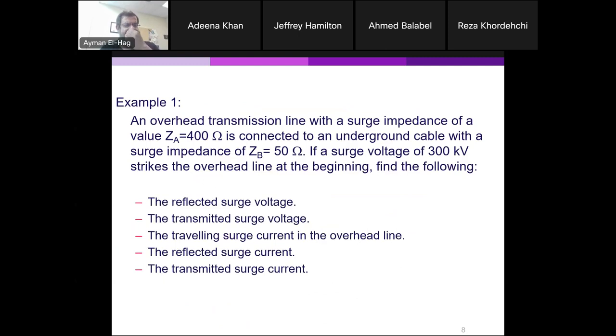Now, let's see this simple example. So we have here an overhead line, transmission line. The surge impedance is 400 ohm. Again, Z is nothing but root L over C. It's connected to an underground cable with a surge impedance, ZB, which is equal to 50 ohm, and this, of the overhead line, is equal to 400 ohm. And these are basically typical values. The surge impedance of the underground cable is less than the surge impedance of the overhead lines all the time.